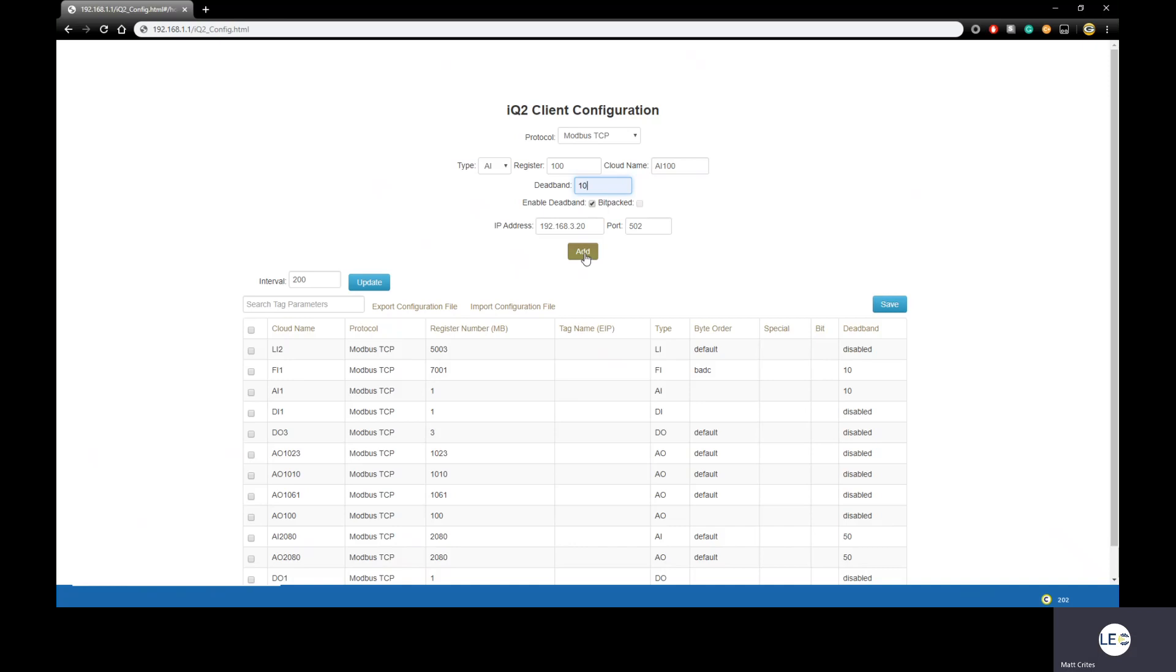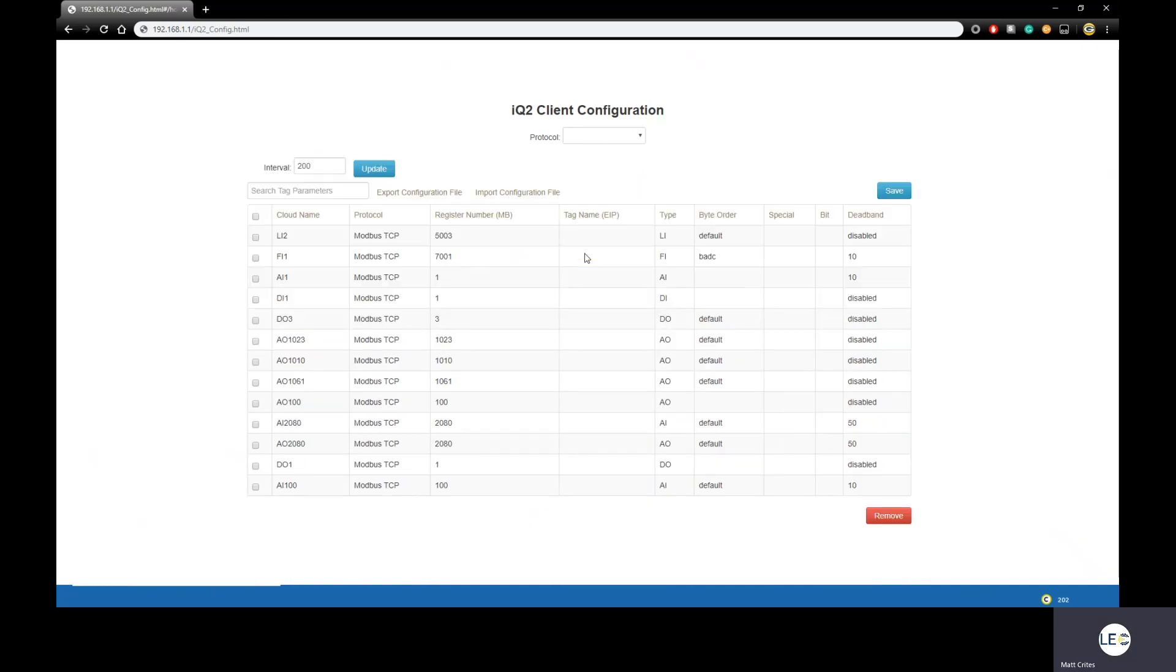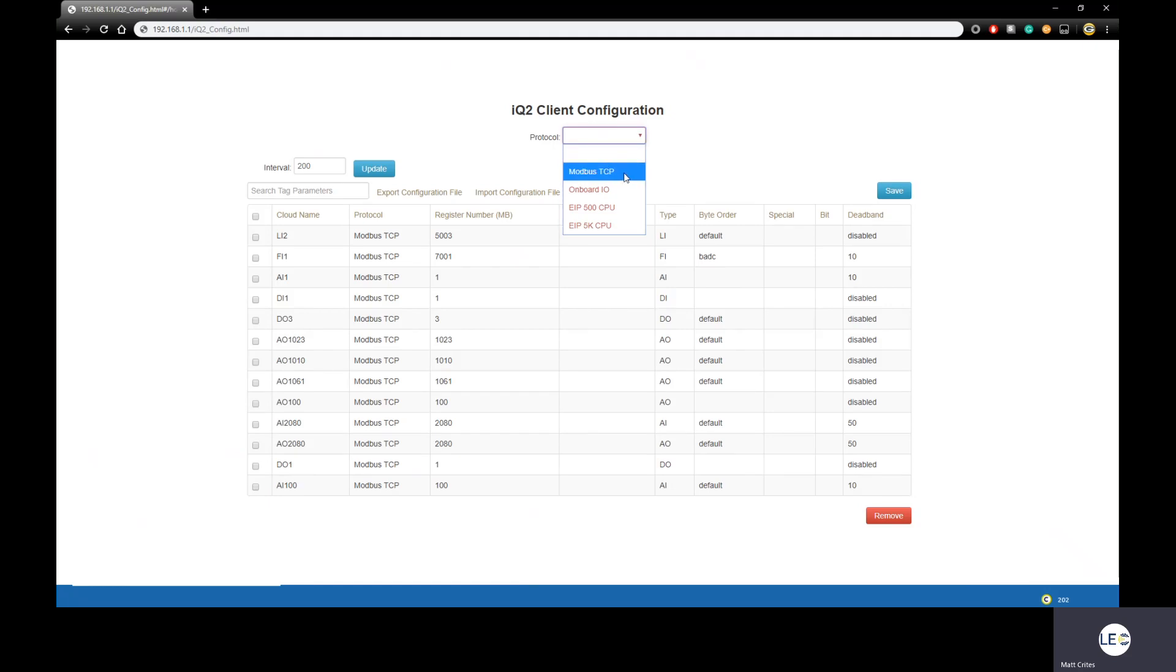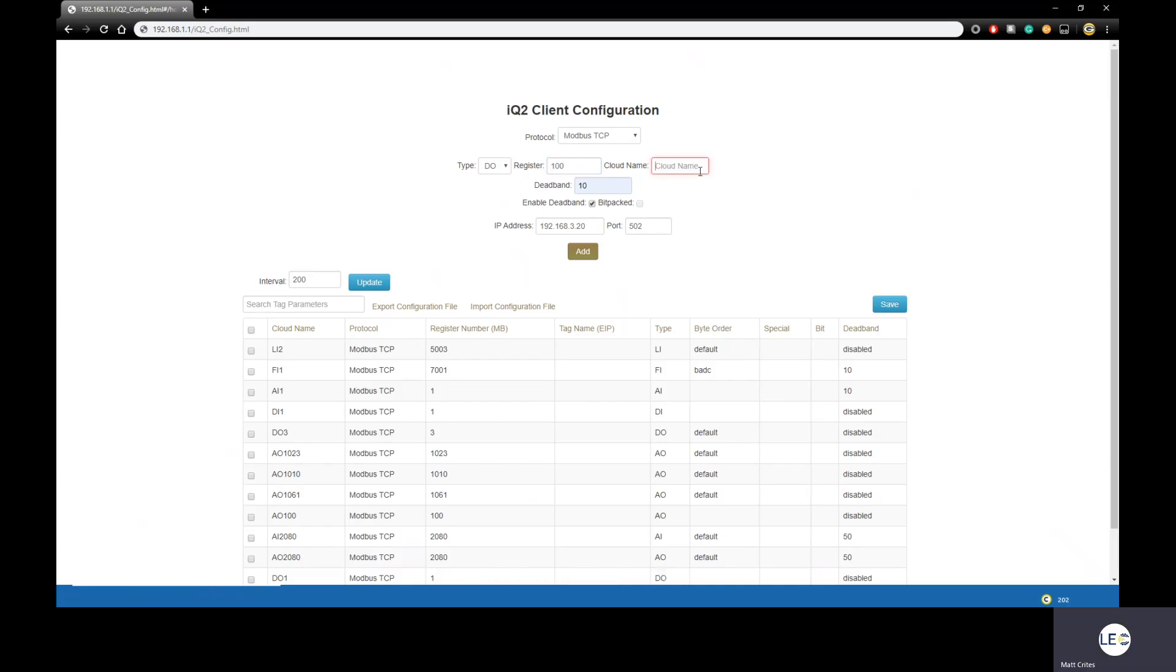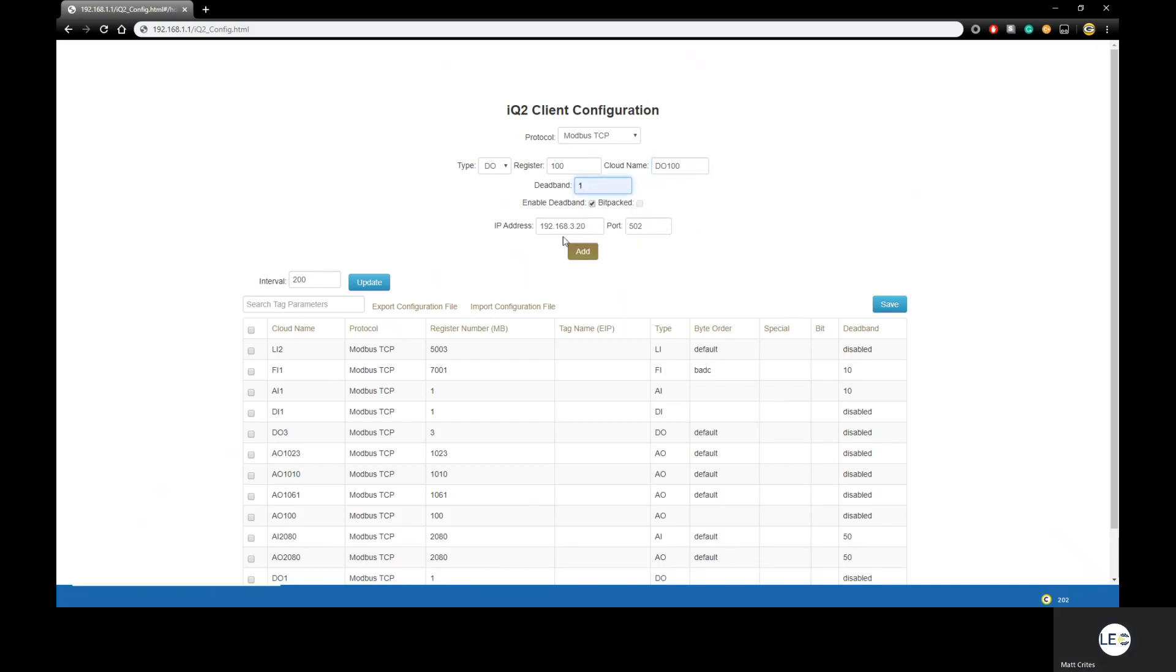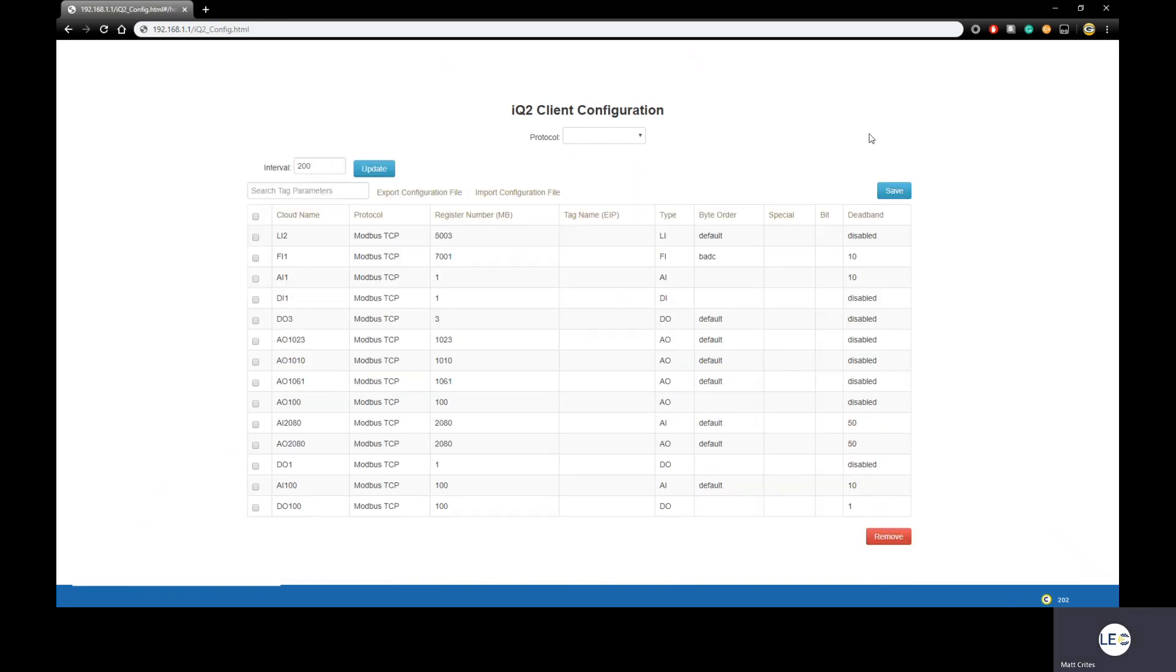When done, we simply click Add. It will now be added to the configuration table below. So let's go ahead and add another one real quick. This time, I'm going to do a DO. Let's say Modbus TCP once again, register DO, we'll make this 100. So what's my cloud name going to be? Type DO, register 100. Cloud name is DO100. Deadband, since it's a digital, I will change that to a 1. And then my IP address, my port remains the same. Click Add.